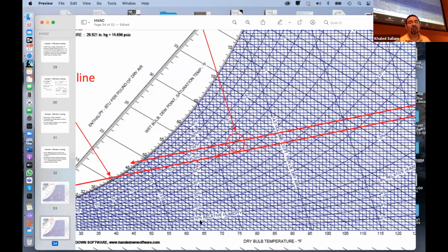So simply, if you have more m dot, you can deliver the air a little bit, not that cold, because there's a lot of m dot that will pull m dot delta H. But if you have smaller m dot, because the ducts are small, because you don't want high velocity, then you'll have to have a bigger delta H for the cold air coming in, so that it can pull all the Q dot L in its way. Okay.